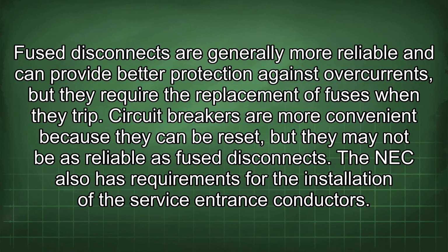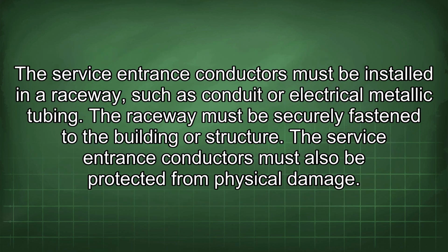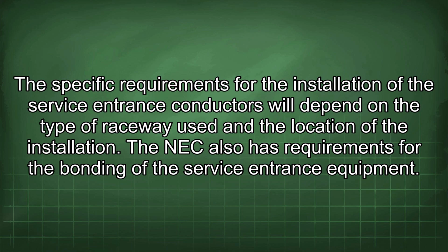reliable as fused disconnects. The NEC also has requirements for the installation of the service entrance conductors. The service entrance conductors must be installed in a raceway such as conduit or electrical metallic tubing. The raceway must be securely fastened to the building or structure. The service entrance conductors must also be protected from physical damage. The specific requirements for the installation of the service entrance conductors will depend on the type of raceway used and the location of the installation.